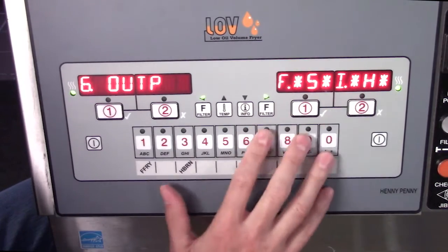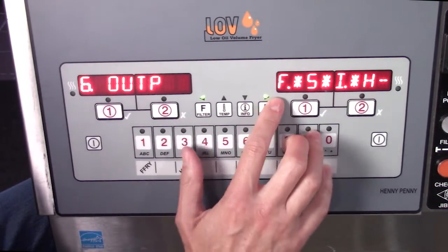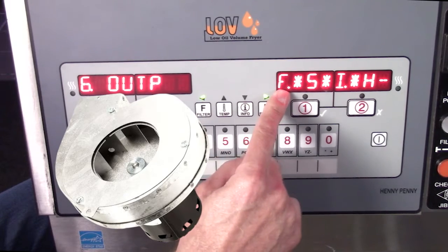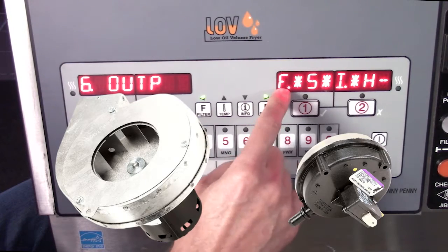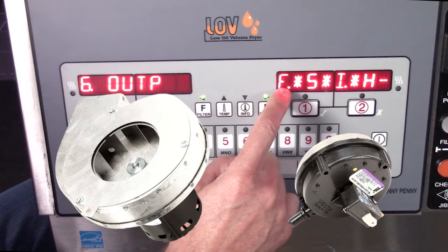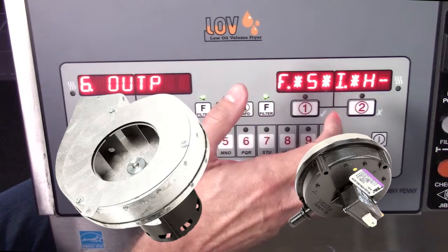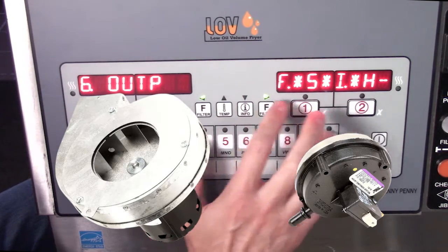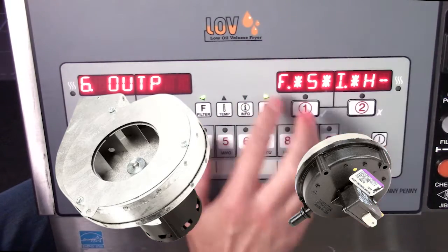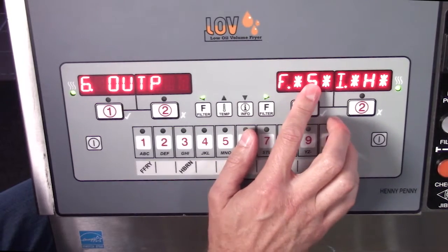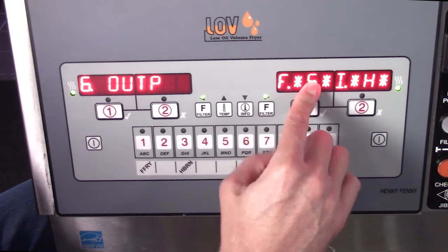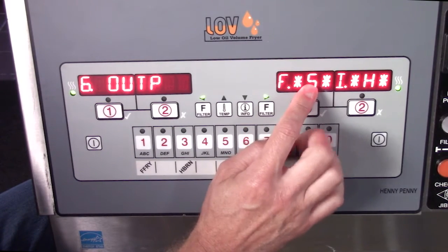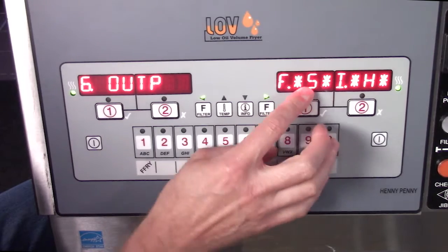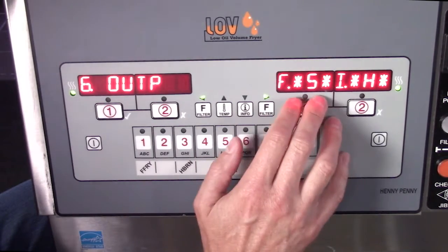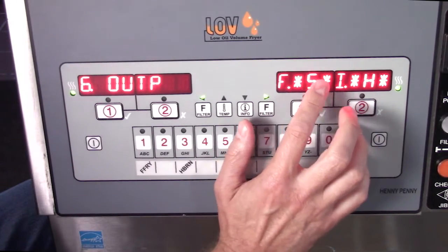So I'm looking here to see that the F is for my fan. This little decimal here is telling me that my pressure switch is closed. So I reached the right amount of inches of water column for my pressure switch to close, and I can go ahead and start my heat sequence. The S has to do with my safety solenoid for international group. So you have a safety solenoid. We don't use it here domestically. So that's telling me it's energized here.